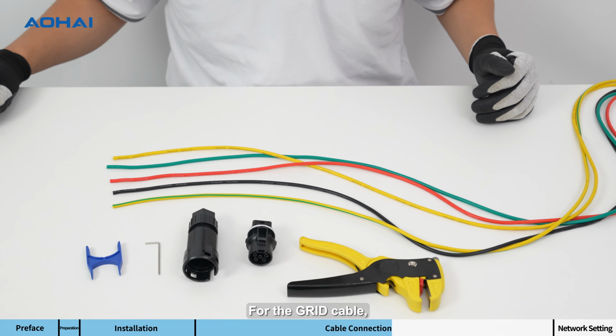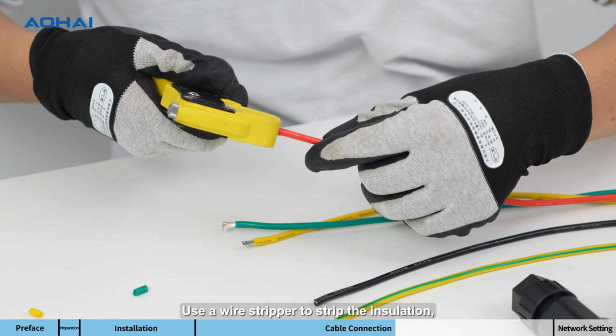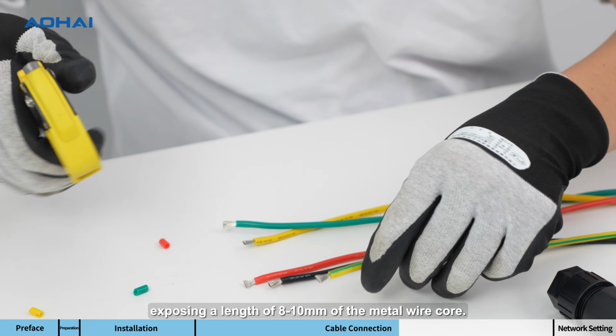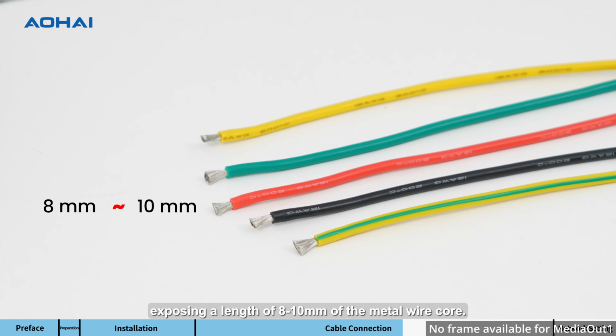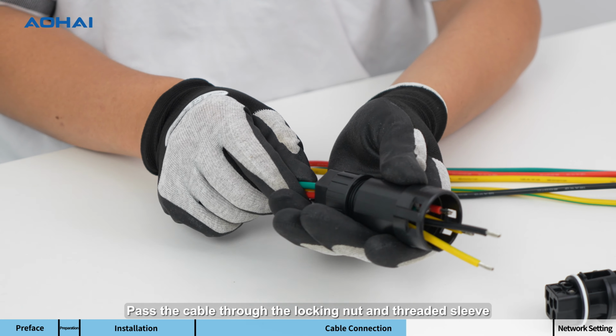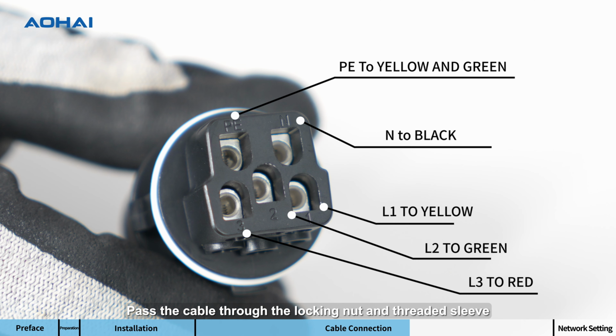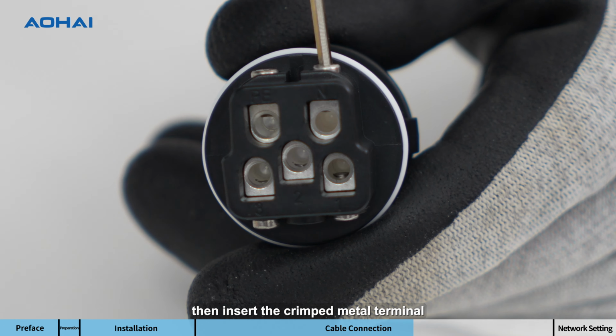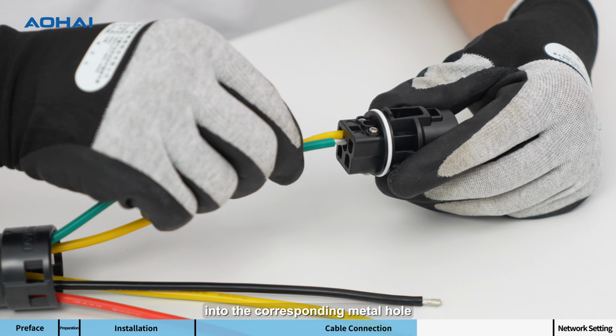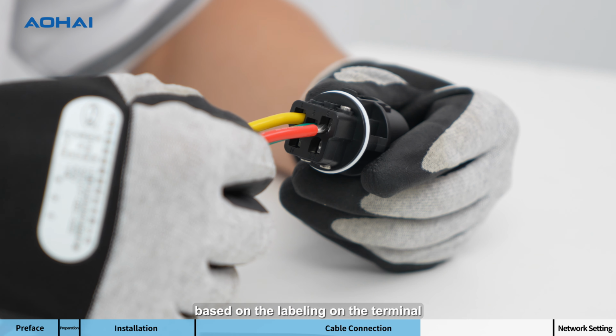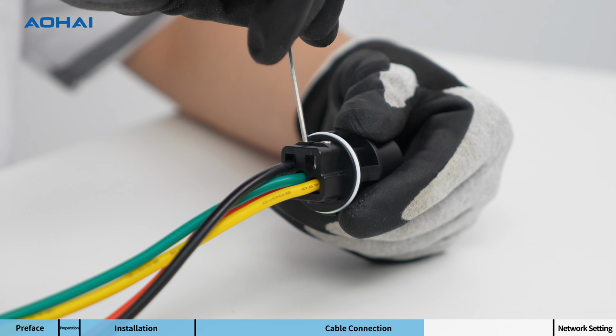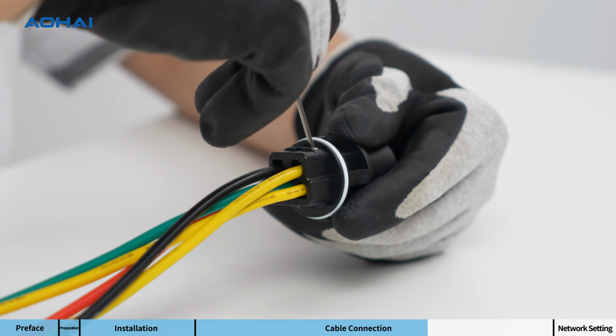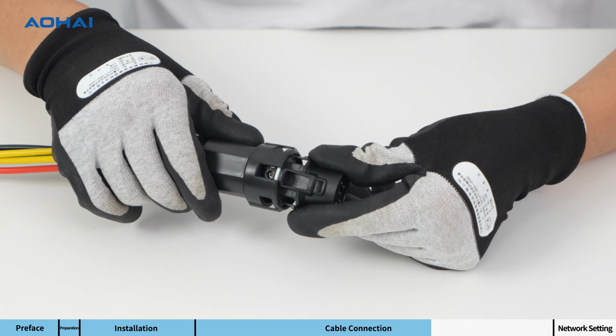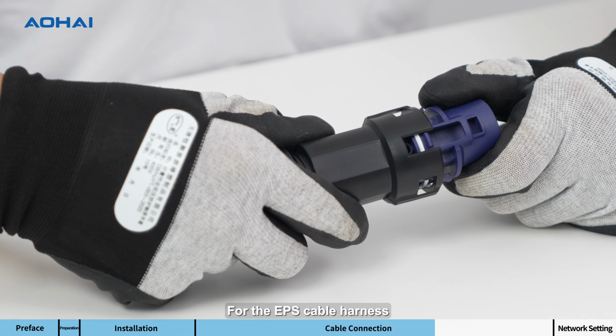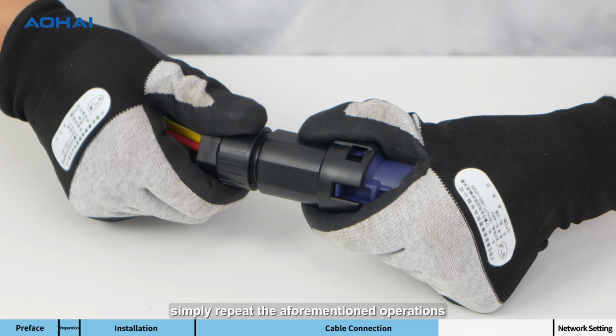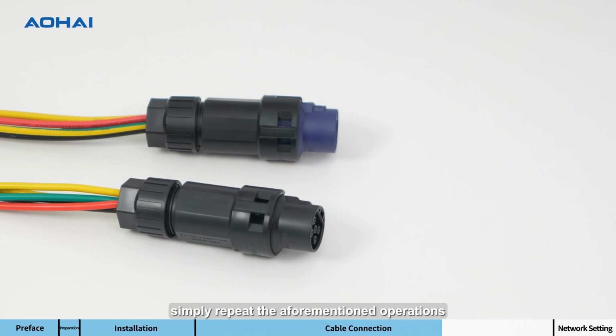For the grid cable, use a wire stripper to strip the insulation, exposing a length of 8 to 10 mm of the metal wire core. Pass the cable through the locking nut and threaded sleeve. Then insert the crimped metal terminal into the corresponding metal hole based on the labeling on the terminal. For the EPS cable harness, simply repeat the aforementioned operations.